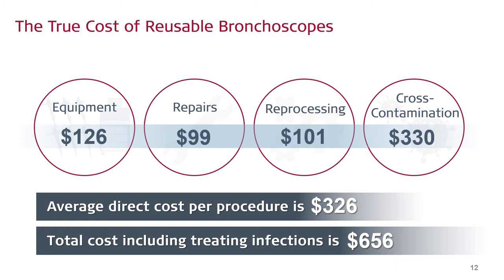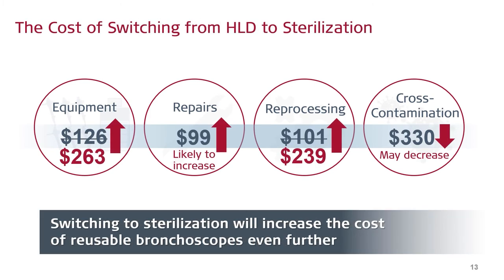One thing to keep in mind here is this is based on the high-level disinfection method of reprocessing. As I mentioned before, guidelines over time are moving to more advanced recommendations on the type of reprocessing that should be done. And if a hospital switches from high-level disinfection to sterilization, studies have shown that the cost will go up. This is data from a presentation at the Endoscopy Suite Infection Control Symposium on what it looks like in terms of costs to switch to sterilization.